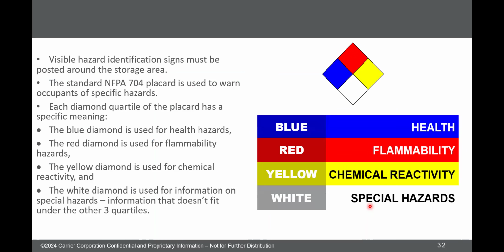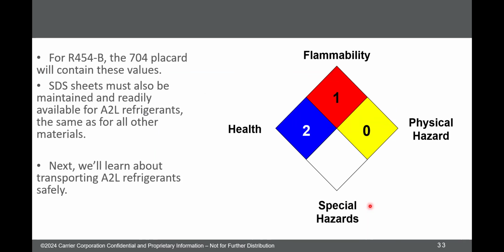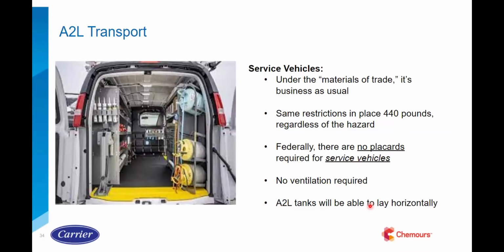And then there are little placards in your storage facility on each area. So maybe you keep all your acetylene in one little metal cage, and over there you keep all your R-454B in another little metal cage. On the side of the metal cage, there are little diamonds that tell you what's in there. The only thing that's really different now from what we've had before is that now something shows up in the flammable section. Before, there was no flammability for our refrigerants, so it didn't matter. But now there's a flammable portion to it.